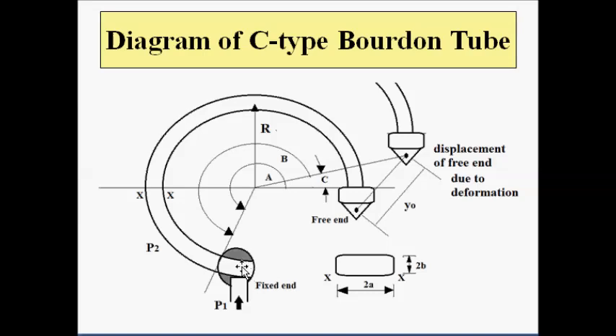This tube is made of a plastic, elastic material, or metallic alloy. One end of the tube is fixed — it is rigid — and is connected to the point where the pressure is to be measured. The other end of the tube, which is elastic and sealed, is free to move. This is the movable end which undergoes displacement whenever there is a change in pressure, or when the pressure inside and outside the tube are different, meaning there is a differential pressure.